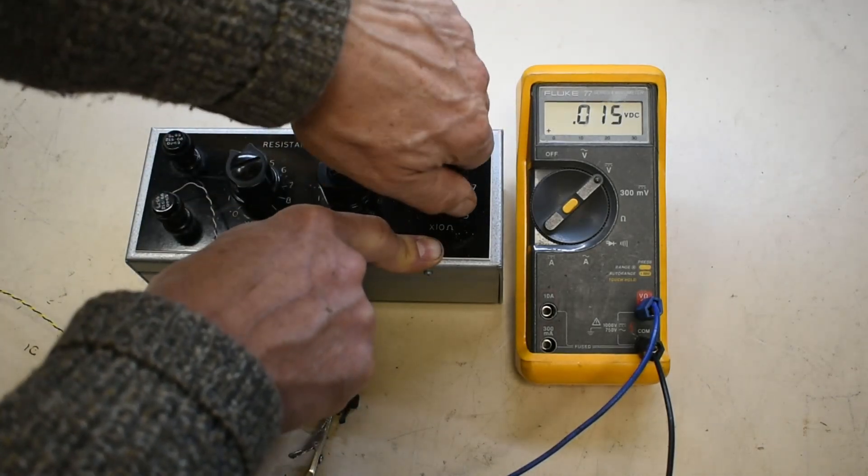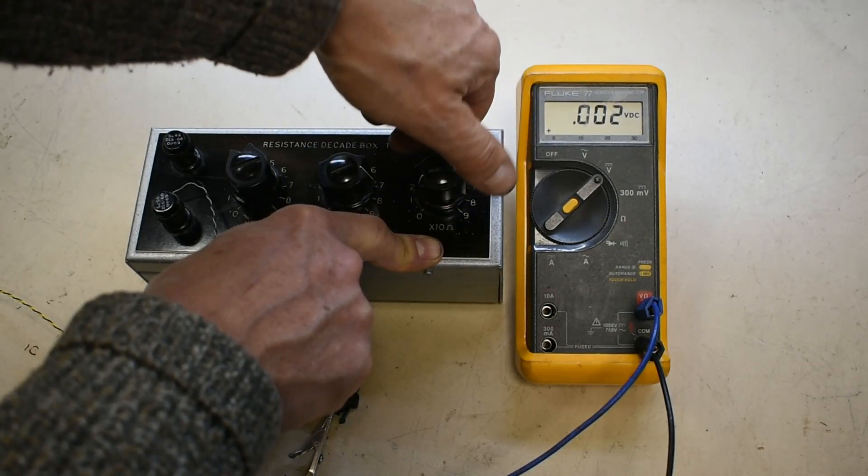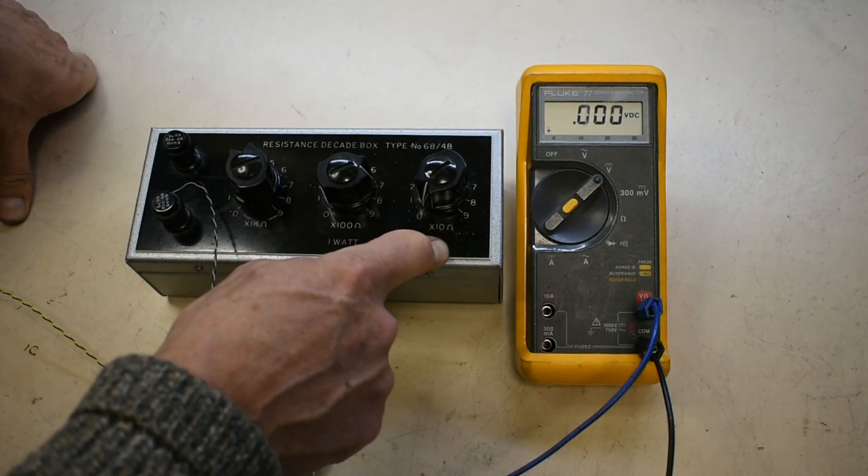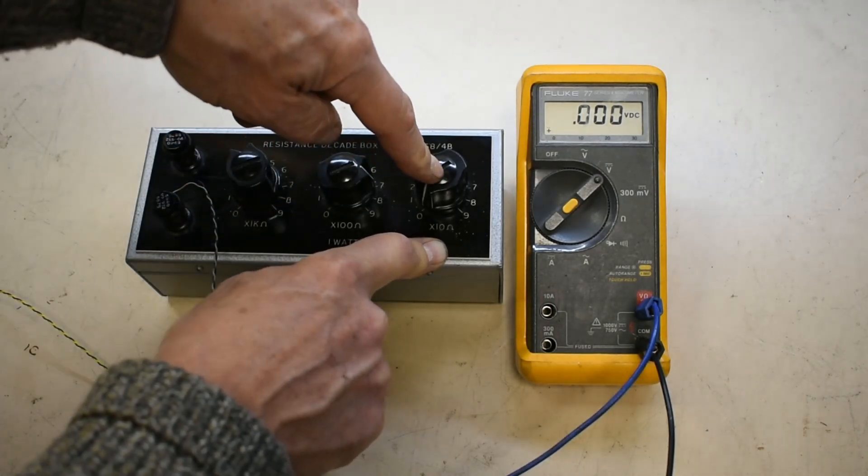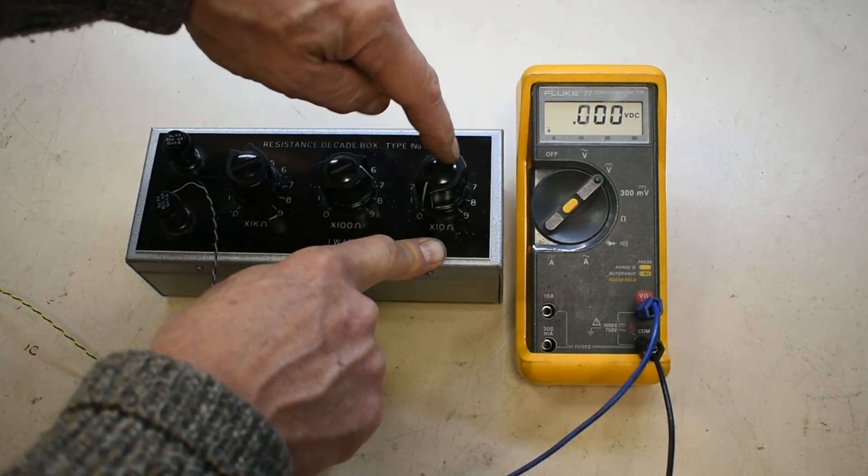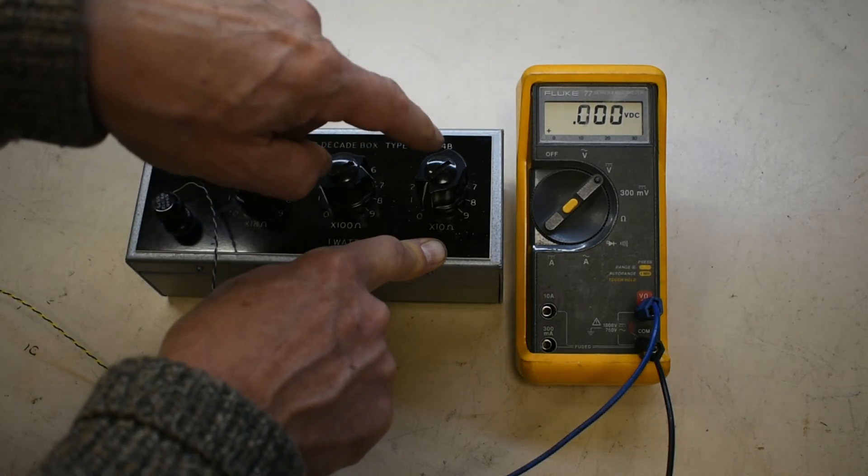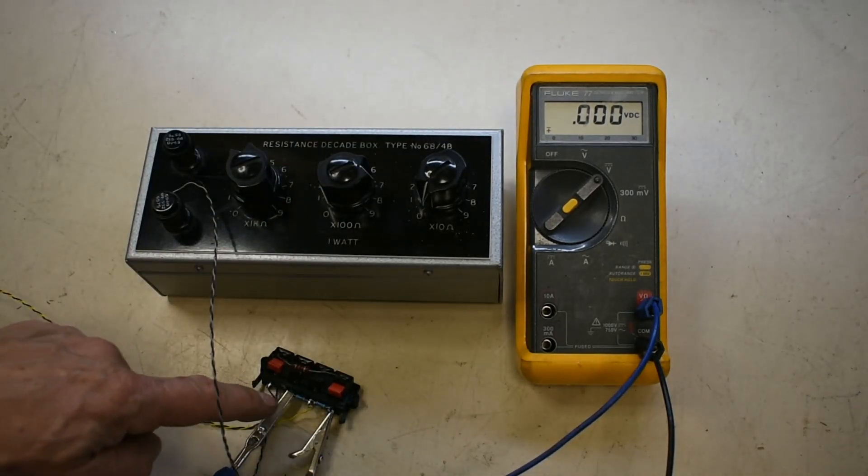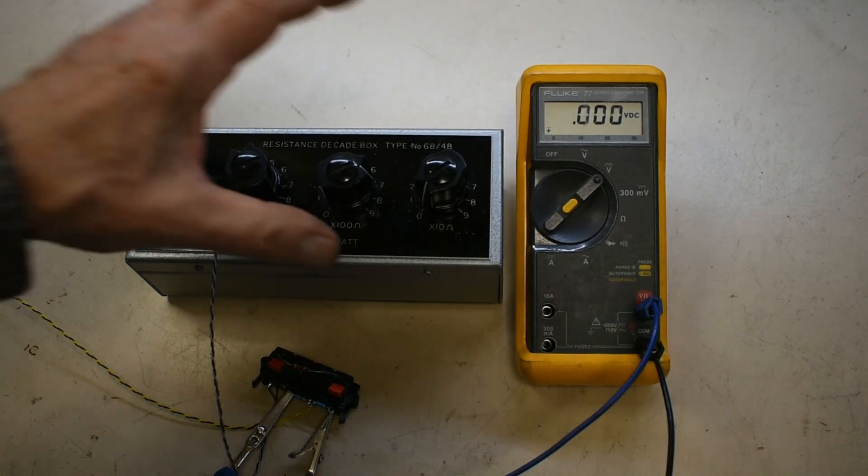I could try this way. There we go, absolutely zero. So we've got a resistance set here of 470. So that's in tens ohms. So that's our 4700 ohm resistor is the value here now. And because our two values are the same here, we know that now is that value of resistance. So we've discovered what our unknown resistance value is by balancing this bridge.